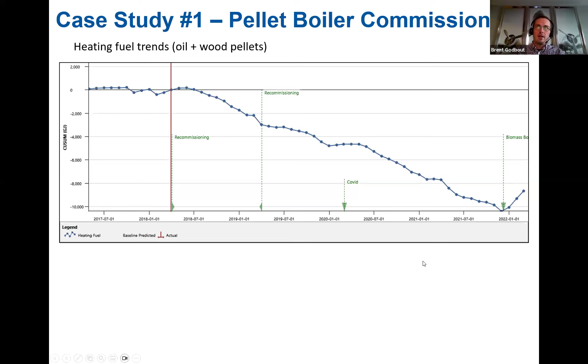In the end, what happened was it was a communication error between the pellet boiler and the old oil boilers. So the old oil boilers still are there as a backup. The pellet boiler takes up or accounts for about 70 to 80% of our heating load. But then in the really cold months of January, February, the oil boilers have to kick in just to get us through those colder months. But what was happening was, because of the old oil boiler communication system, it didn't communicate well with the pellet boiler. And ultimately, the oil boilers weren't allowing our pellet boiler to take the lead.